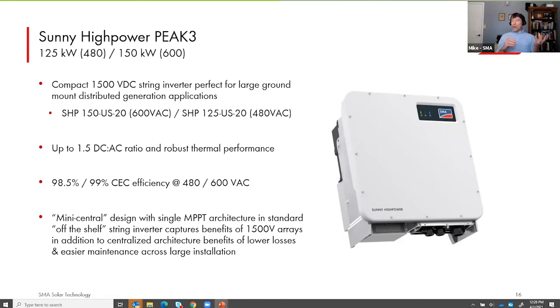Along the lines of plant design, with the Peak 3 you also get benefits from this architecture by placing more inverters together in a centralized plant design, as if you had a single central inverter. Putting multiple Peak 3s close together provides maximum benefit for the system owner: DC power is transmitted over longer distances at higher voltage, giving lower line losses than on the AC side, since all inverters are close to the point of interconnection, and the lower voltage AC run is shorter. You also get all inverters close together for easy communication connections and easy O&M benefit. So it provides all the benefits of a 1500 volt utility scale plant design. With this centralized architecture, you get the benefits of smaller inverters plus the benefits of that layout design. A very powerful device.